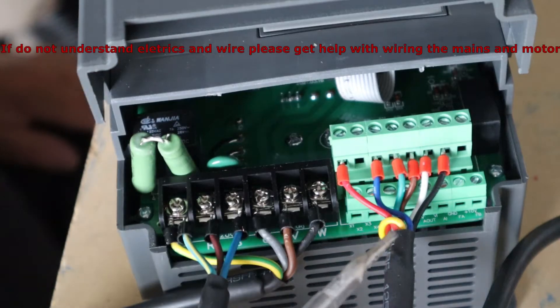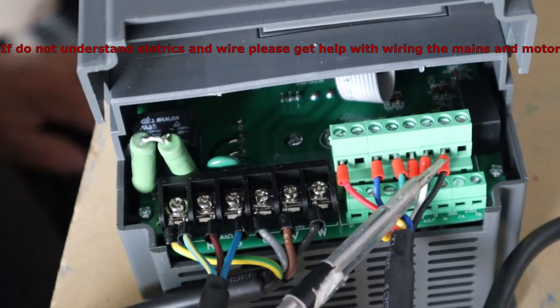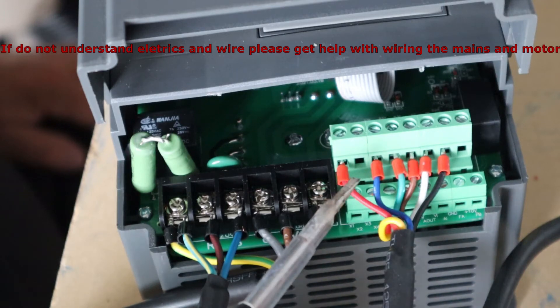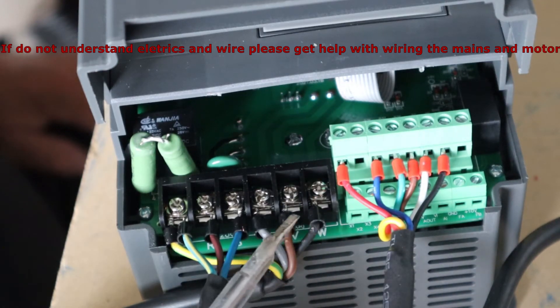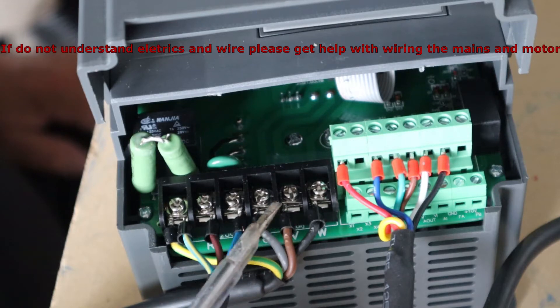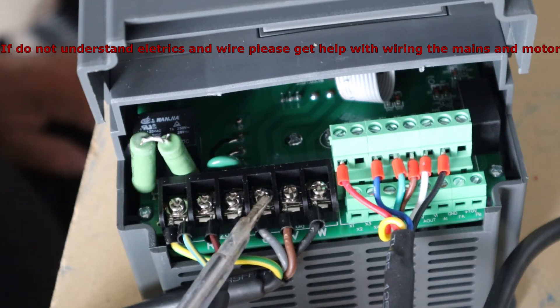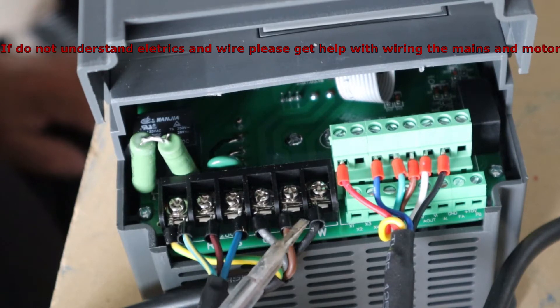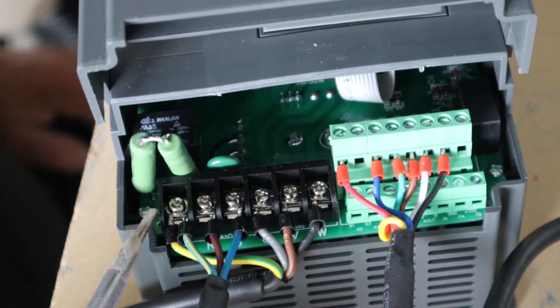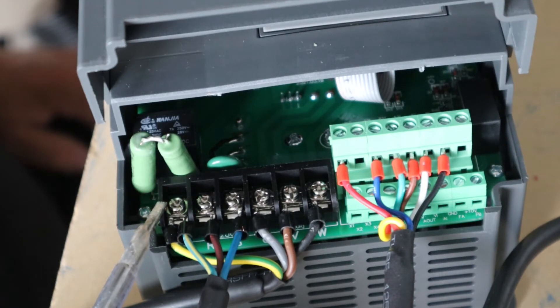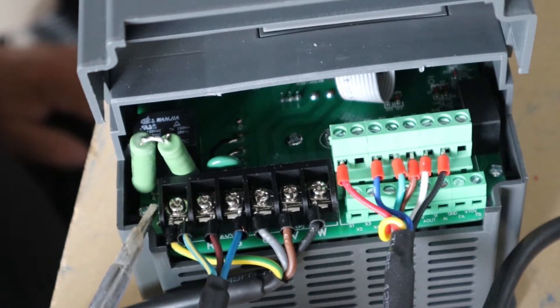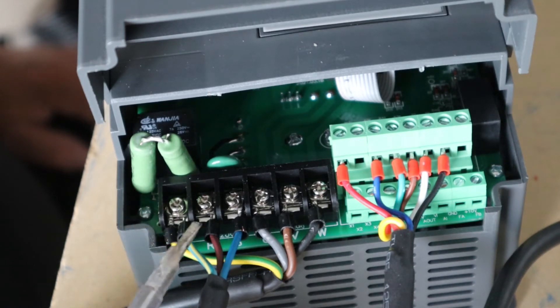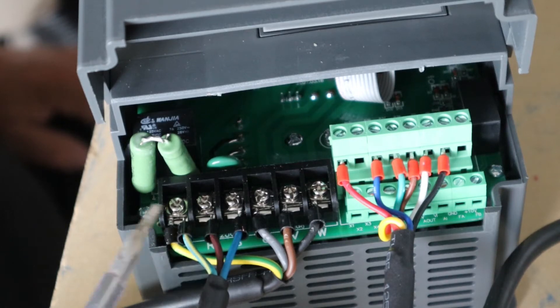This is your controller. That one there is all your controller wire. The first wires going into it or coming out of it are your motor. Now don't forget your earth on your motor must go to the earth coming in. Your earth cannot be switched. You cannot put a switch on your earth. It has got to be continuous. Continuity has got to be all the way through. And then you go live next to your earth and then neutral.